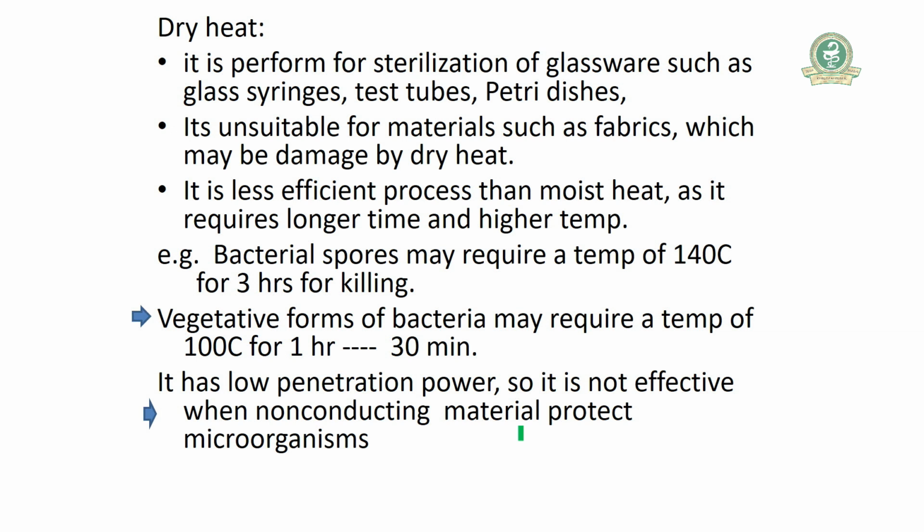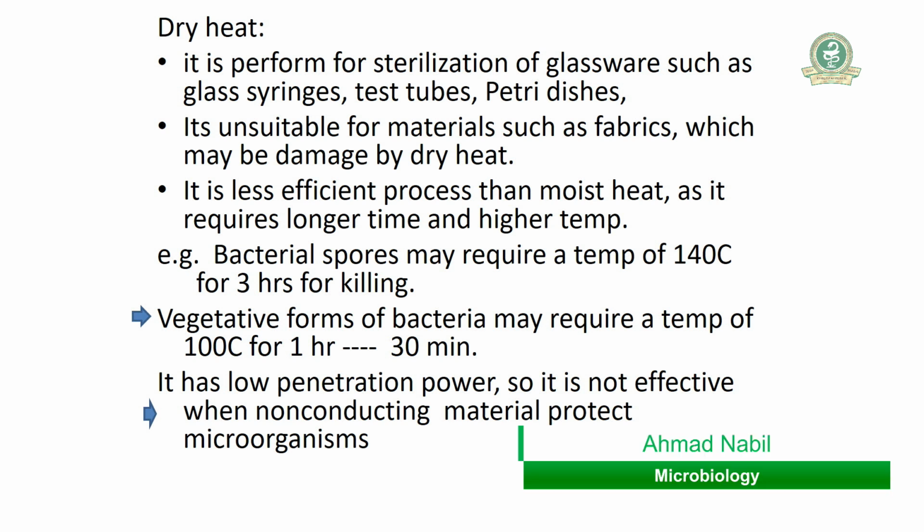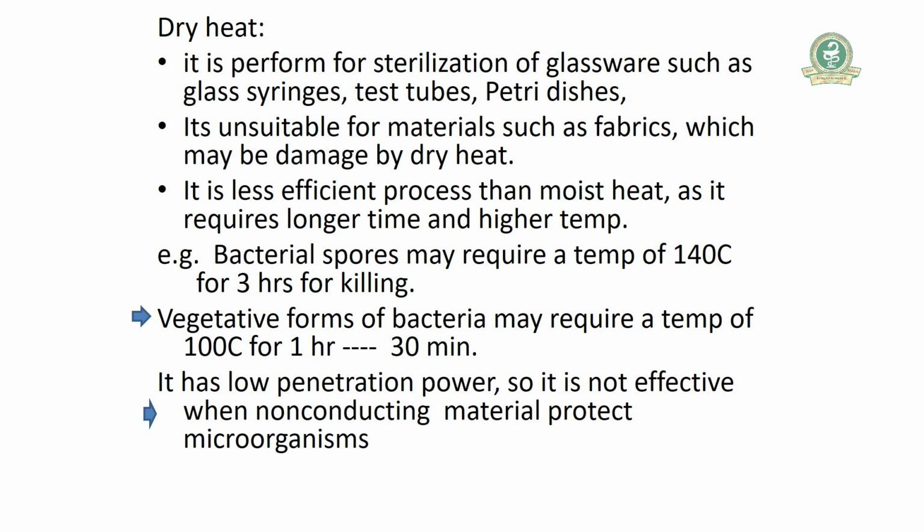Next, it is a less efficient process than moist heat, requiring a higher temperature. For example, 140 degrees centigrade for 3 hours for killing, or 100 degrees centigrade for 1 hour. It has low penetration power.